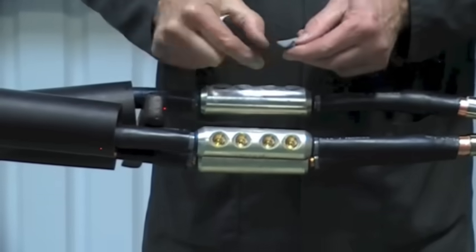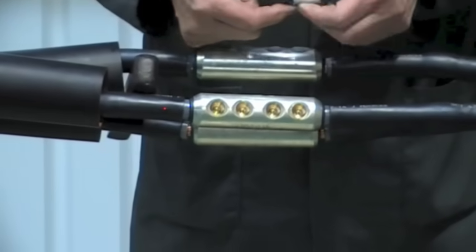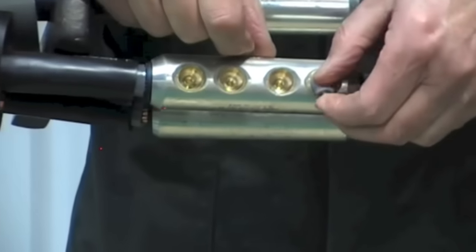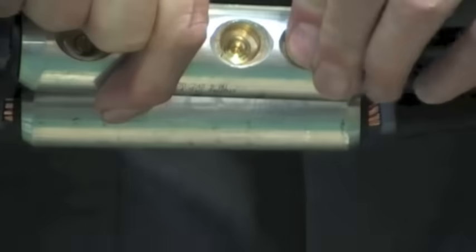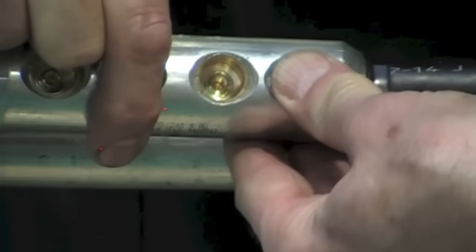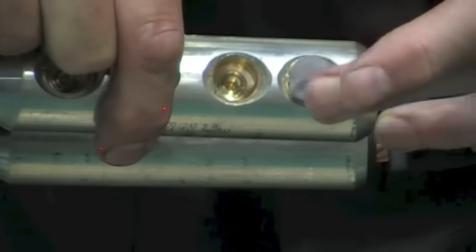Some connectors may leave voids where the bolts shear. With this type we supply HV mastic putty tape which you apply into the voids filling up to the surface of the connector.